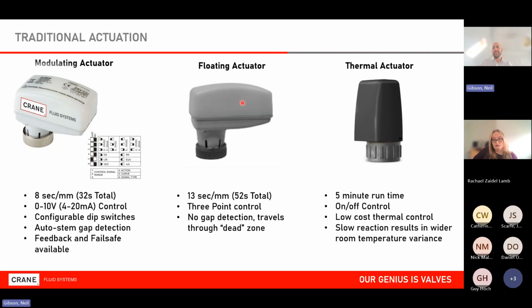And then we get to the slightly less intelligent ones. So we've got a floating type actuator, a bit slower to react. And then we've got the lowest cost option, let's call it, of a thermal actuator. Again, very slow to react. Typically, you can have 0 to 10 volts. I wouldn't personally choose that, but typically on off. And therefore reacting in a wider room temperature variance as well, a wider band. The most intelligent it gets with this is that feedback feature. Other than that, it doesn't give us much back into the system. And as I said, that's been used quite regularly over the last several years.